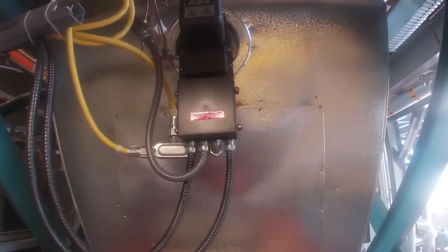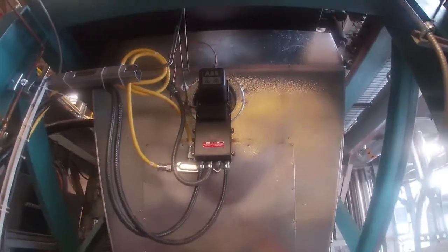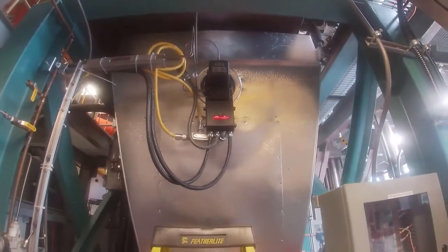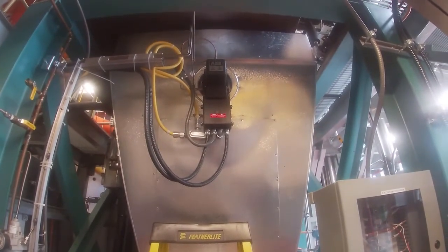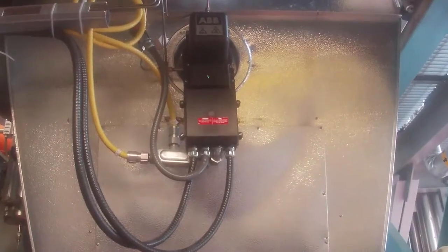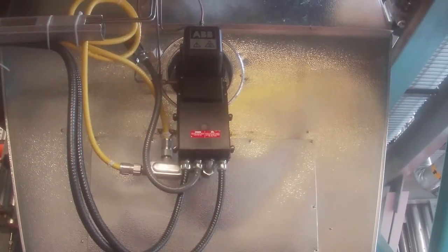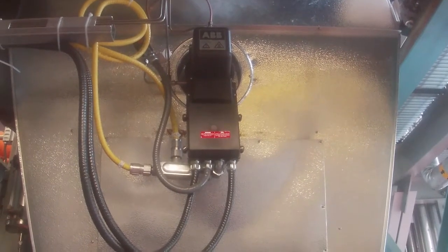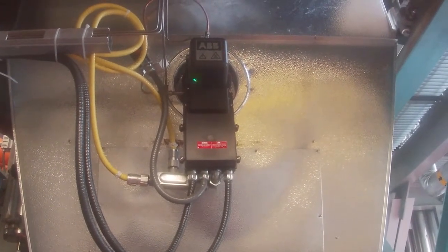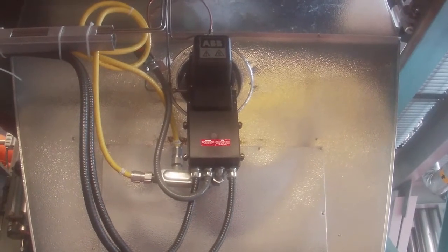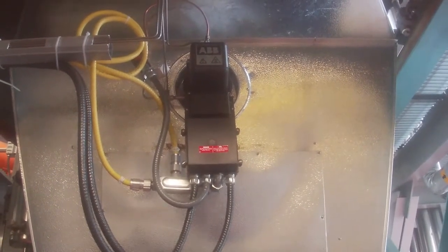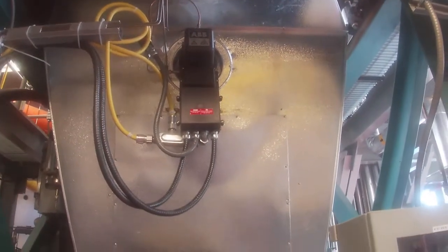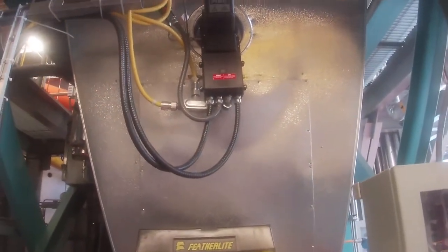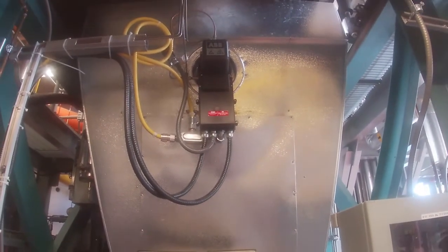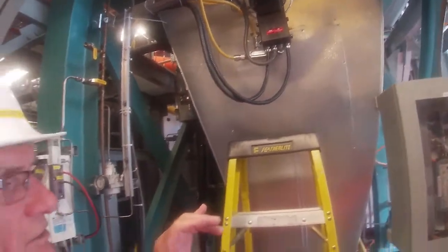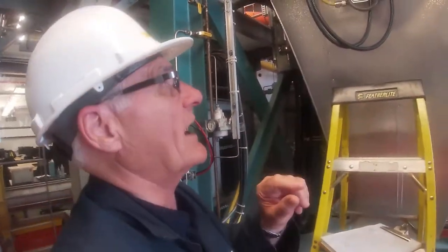So this is an analyzer that is extractive. It's not in situ, but it extracts the sample out and it maintains the temperature high enough that no water will condense and there won't be any damage to the cell itself. So internally, this guy is hot. That flange is running with heaters inside it, and it's being heated up to a controlled temperature. And then inside it, there is another set of heaters, and that raises the carbon monoxide cell or combustible cell up to even higher temperature.